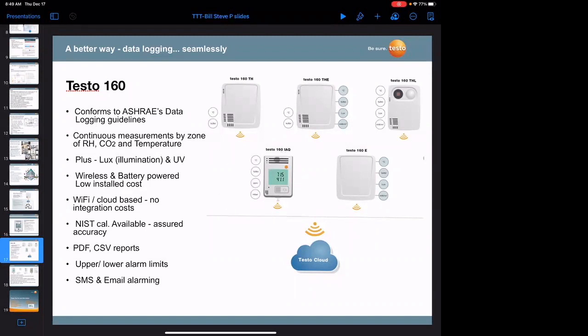We can talk about the proper location to mount these, but in classrooms you want them above reachable levels for kids so they don't tamper with the unit. It's good practice to locate them close to the return air in a space, so you get a good sampling of total CO2, average temperature, and humidity. In a cafeteria, I'd put one by the return and maybe one more centrally located, away from major transition areas, not near doors to other zones, one in a quiet area and one near the return.